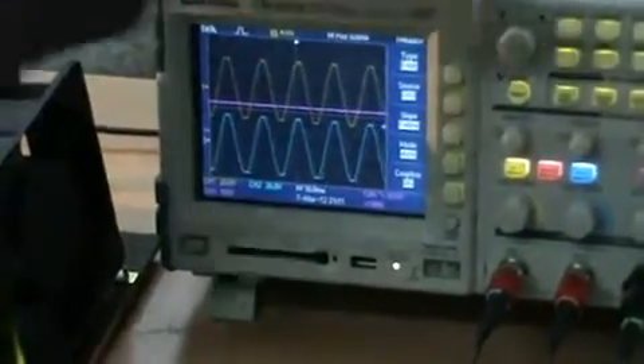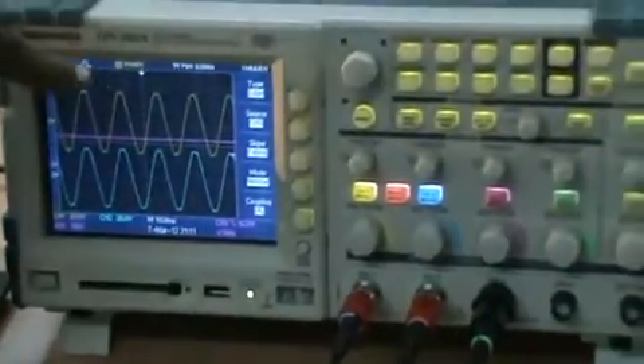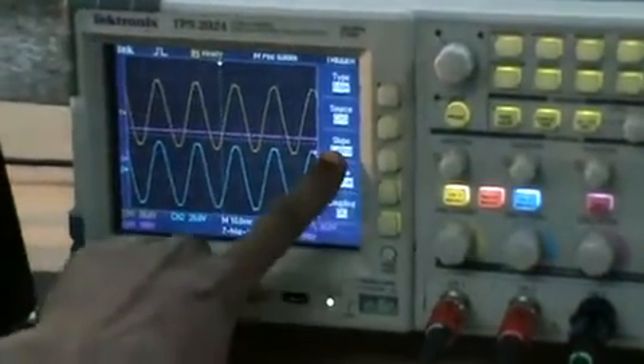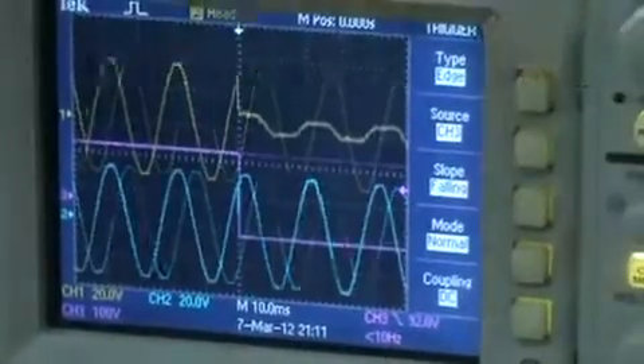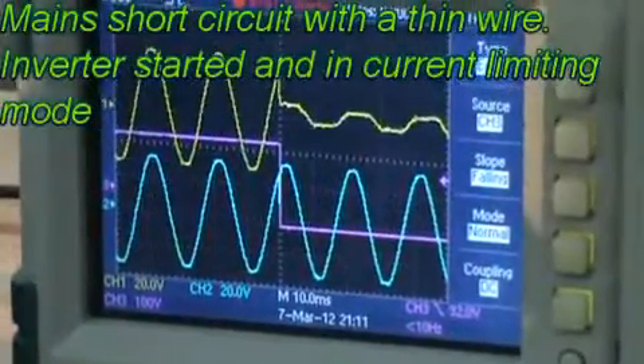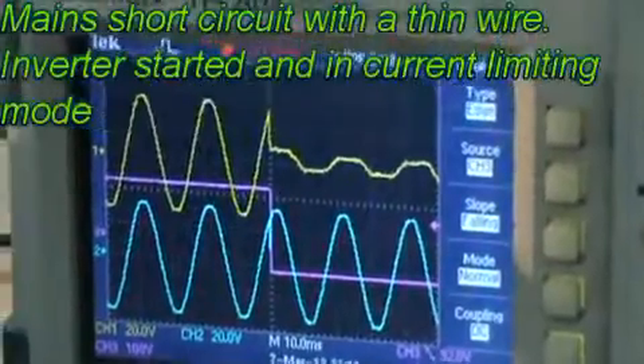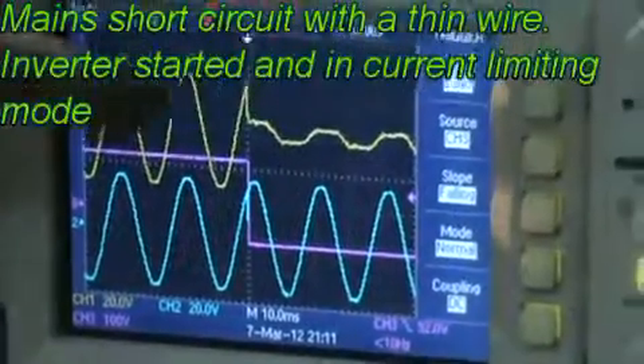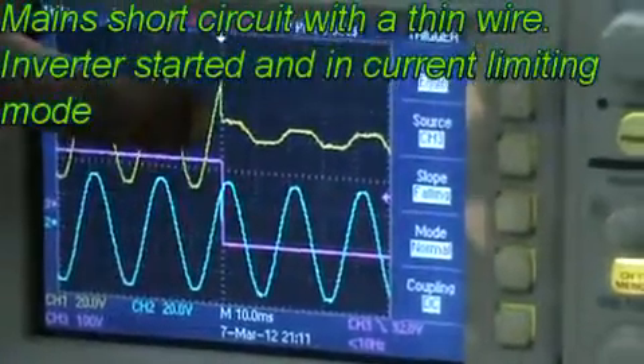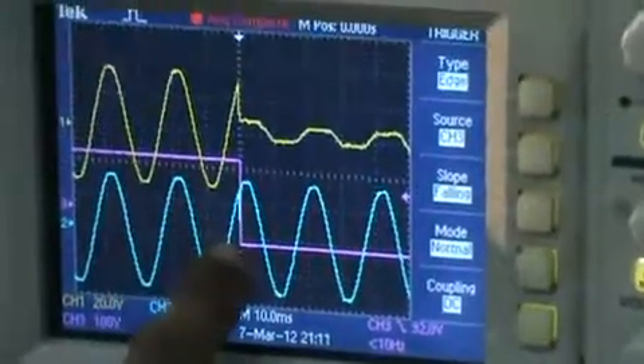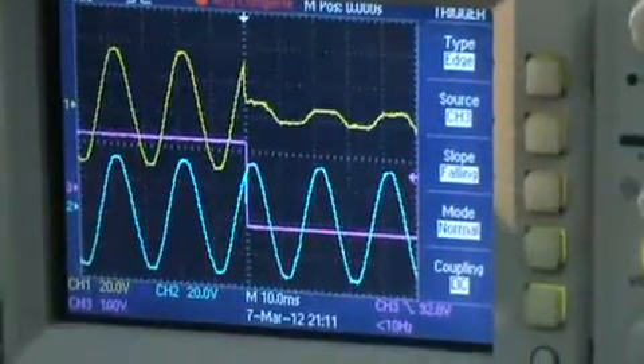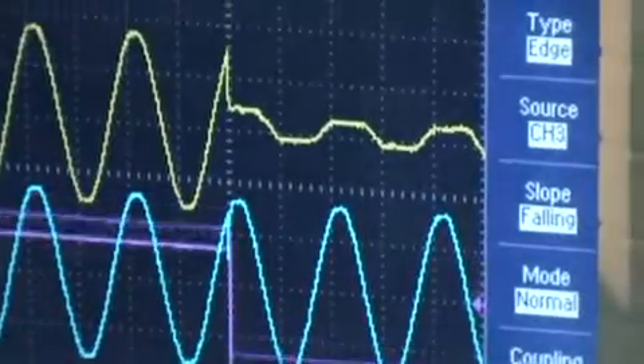Now I am going to short circuit. Before that I am putting the CRO in single shot mode. So the short circuit time will be captured, you can see this is the falling edge that triggered. Now see, I am going to short circuit. See, now I short circuited, here only the short circuit happened. Then it tripped immediately. You can see this pink waveform tripped immediately.